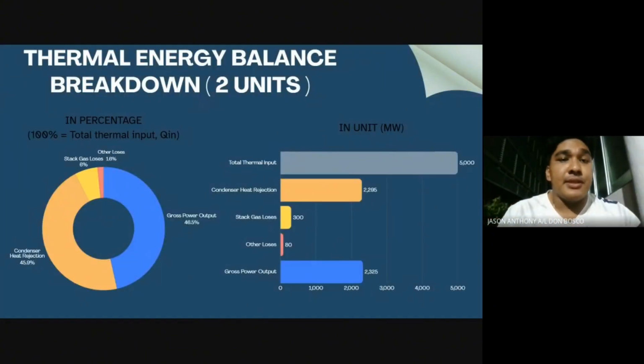Now let's jump into the thermal energy balance breakdown, which is for two units. Now we show it in percentage and also in megawatt. The total thermal input is 5000 megawatt. And then the condenser rejects 2295 megawatt. There are also losses like stack gas losses, which are about 300 megawatt. This is all approximation. And also there are other losses of 80 megawatt, and also a gross power output of 2325 megawatt.